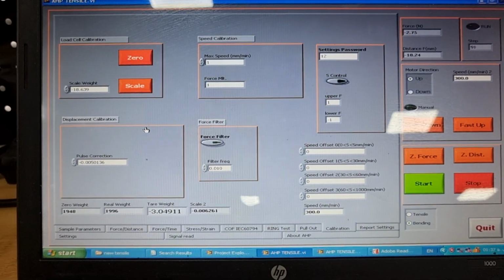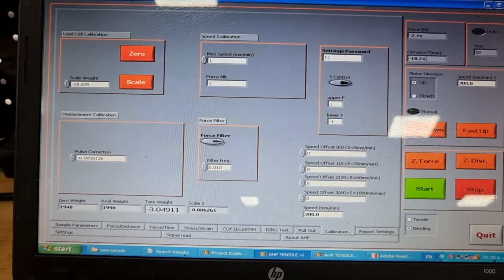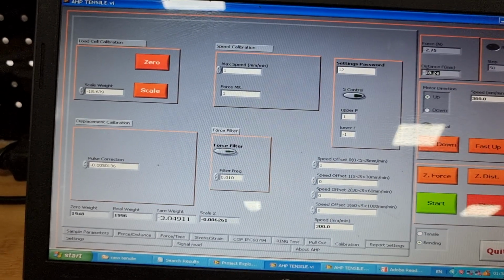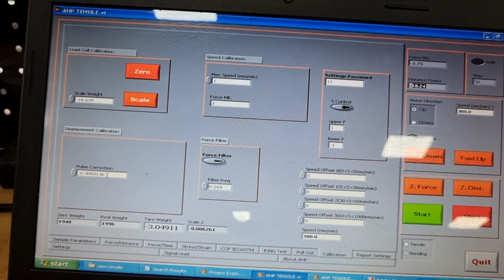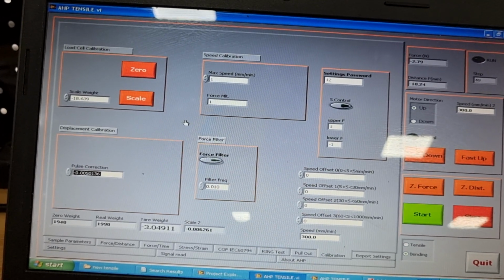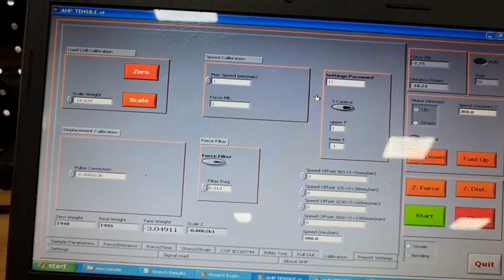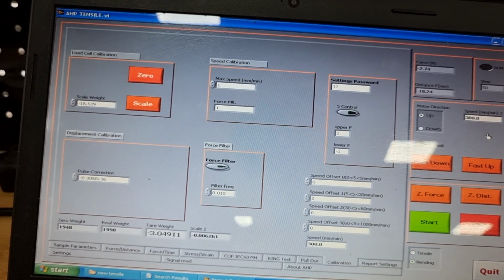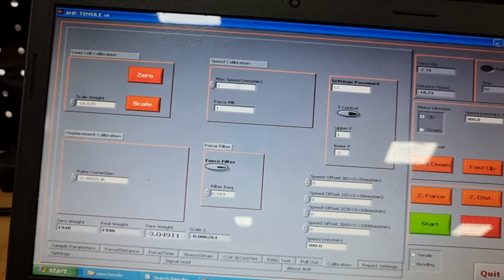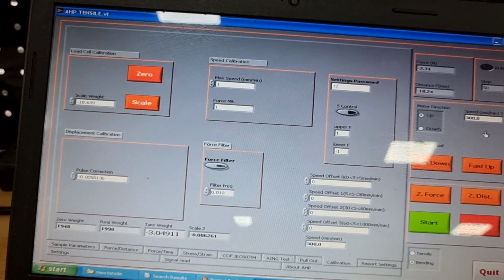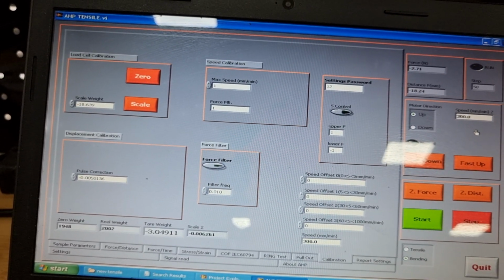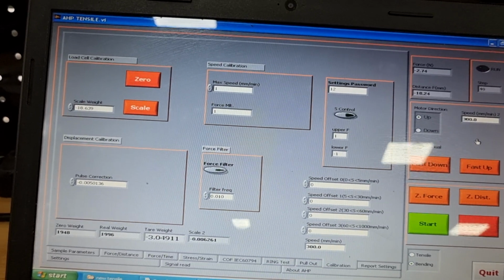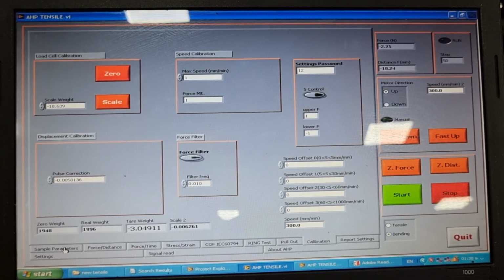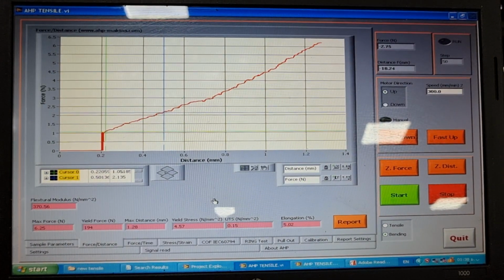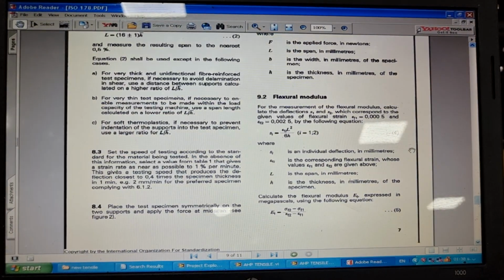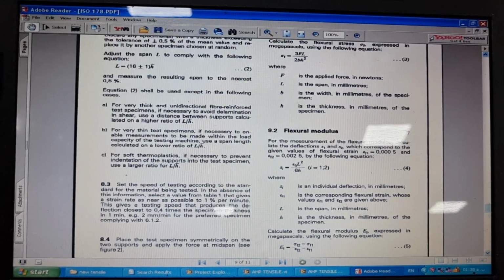For the displacement calibration here, you have a displacement showing the distance of travel. You will calibrate using this factor. And for the speed calibration, you have the parameter here. That's all. It's very easy to calibrate. And then I'm going to use the machine for flexural measurement. The flexural measurement is according to ISO 178.